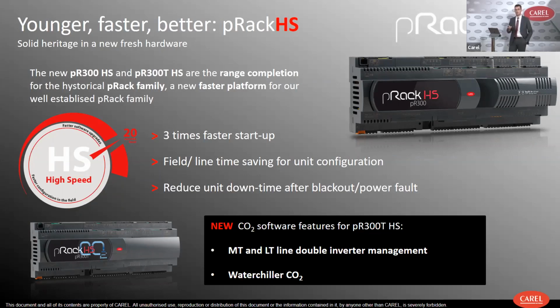So what does it mean? What are the benefits of higher speed for the controller? It's very simple. For example, you can save time on the field during the commissioning by making the configuration of the system, but you can save time also during the unit configuration in the factory, because upload, configuration, download, and software modifications in terms of parameters are very, very fast compared to the previous one. Of course, another important benefit is the reduced downtime of the unit in case of blackout, because the reboot of this controller is faster compared to the previous one, and we can avoid a lot of alarms that can come when the controller is offline in these special conditions.